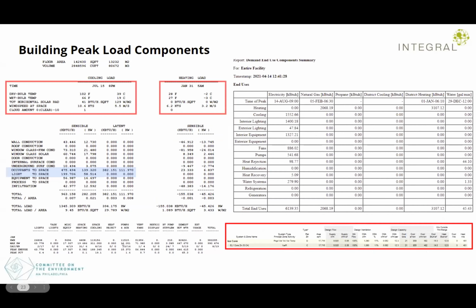So once I've figured that out, I want to zoom in a little bit and look at the building peak load components. As in, what are the end uses, or heat gains or losses, in the building that add up to the peak load in that particular building. So immediately the first thing that I see is that the cooling load occurs on July 15th, which is okay. But what if this occurred in a swing month? So I want to ensure that my inputs and my assumptions are right so that the peak load occurs at a time that I think would be appropriate for that building, space type, and that climate zone. And likewise for the heating load.